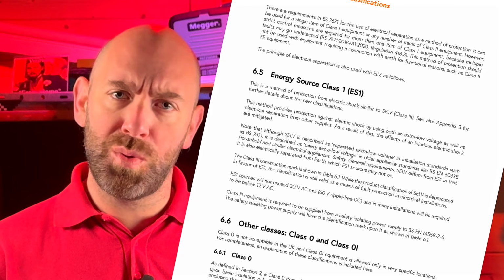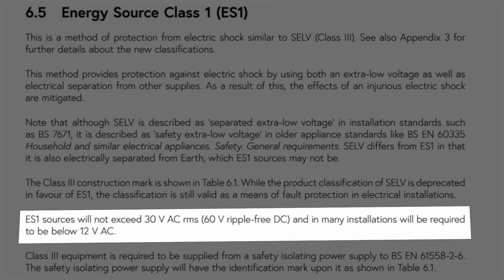Energy Source Class 1 or ES1 is similar to SELV in the fact that it uses an extra low voltage to reduce the shock risk. ES1 sources cannot exceed 30 volts AC or 60 volts DC. In many installations they are below 12 volts AC. The key difference is SELV is electrically separated from earth and ES1 does not need to be. ES1 limits the shock risk through low voltage.